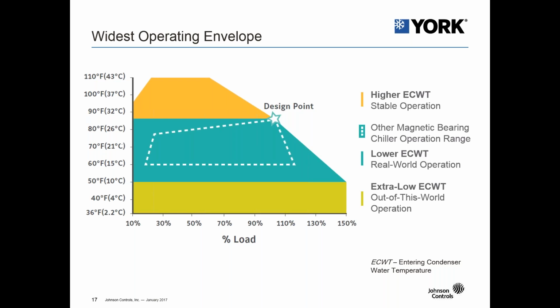So when we look at the capabilities of the mag bearings in terms of an operating envelope, what you'll see on the left-hand side is entering condenser water temperatures that would go in from the tower into the chiller, and then across the bottom you see percent load for the chiller. And what we have in the inside dotted white line is other magnetic bearing chiller manufacturers' operating range that they're showing valid operating points for their package offering.